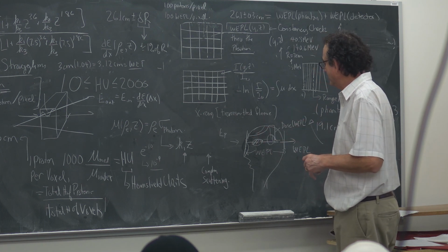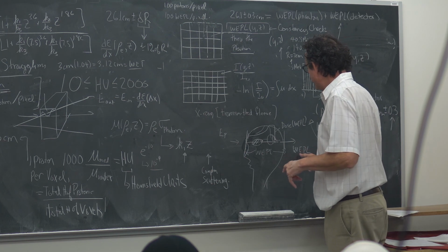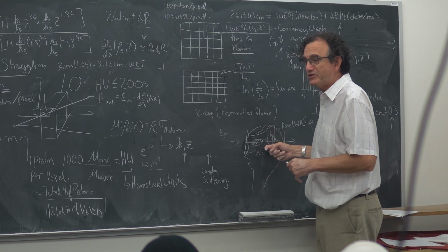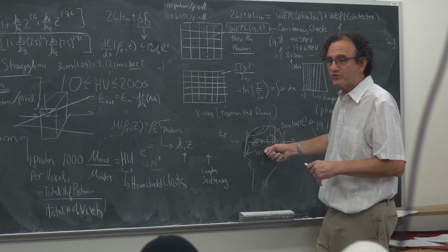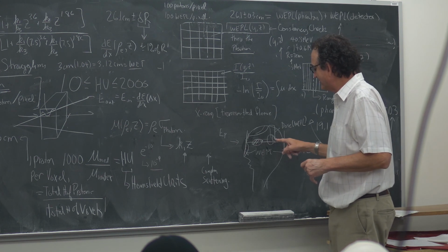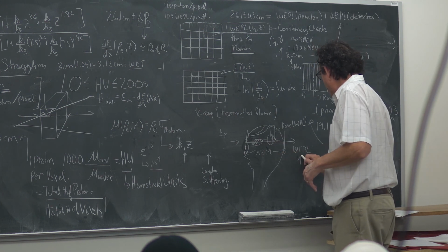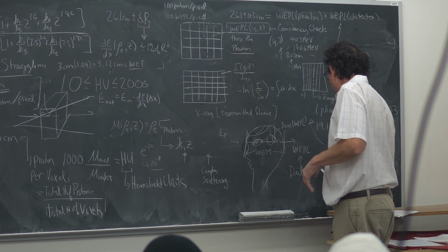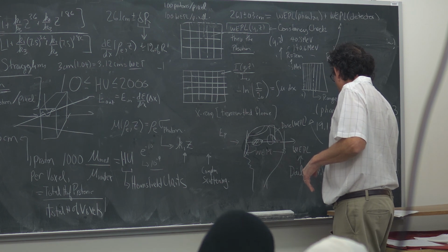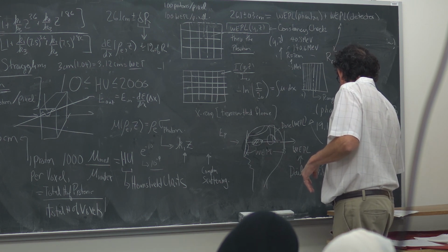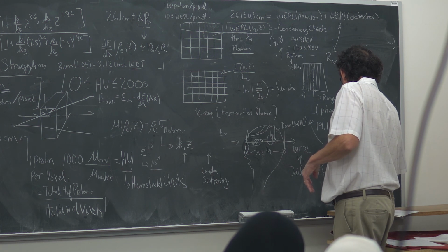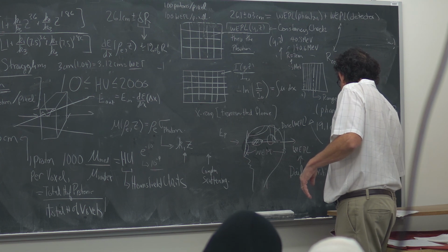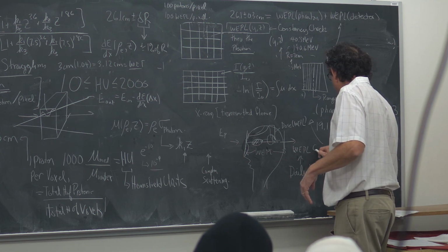It usually happens that if there's been a change in the WEPL, then it's really good evidence that you should at least recheck or re-image the patient and replan them to make sure that the dose being delivered is stopping at the correct edge. This is a daily verification, which one can do for proton therapy patients. And it's a WEPL constancy check.